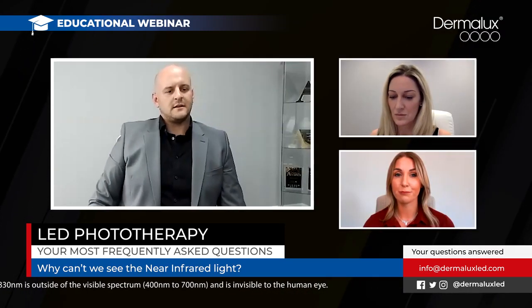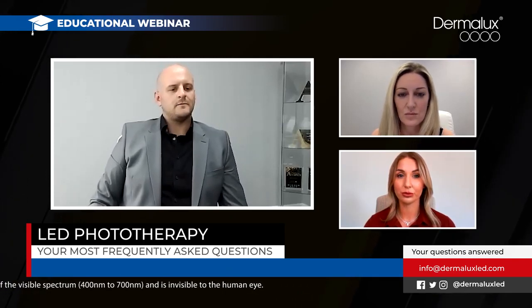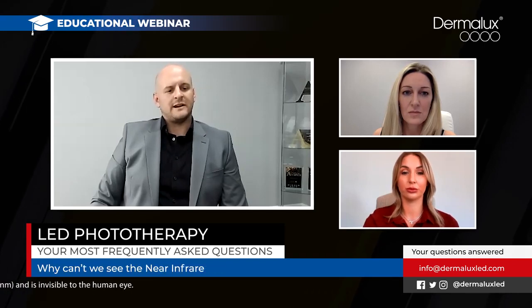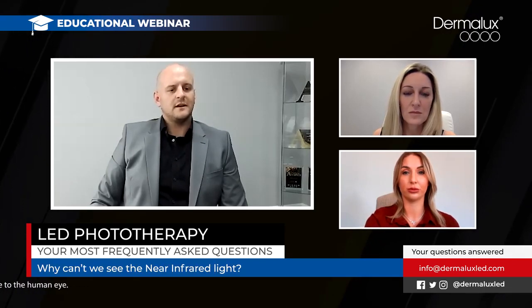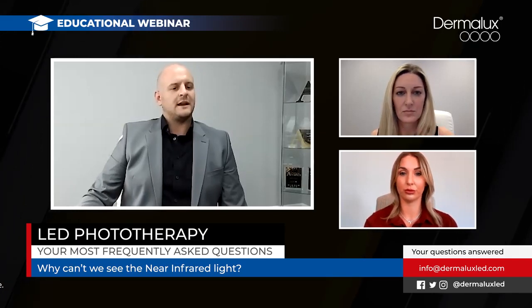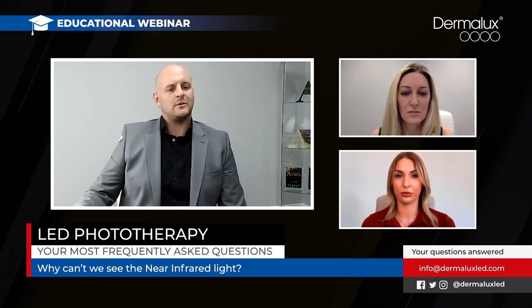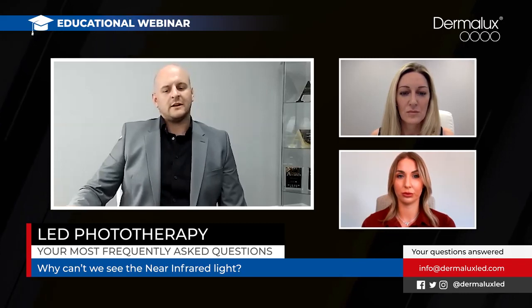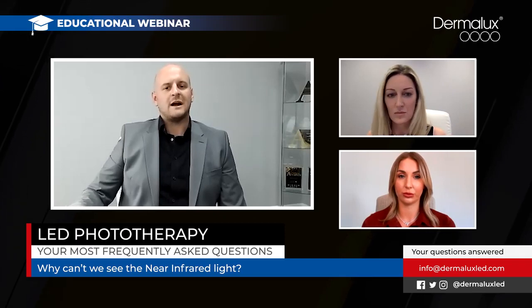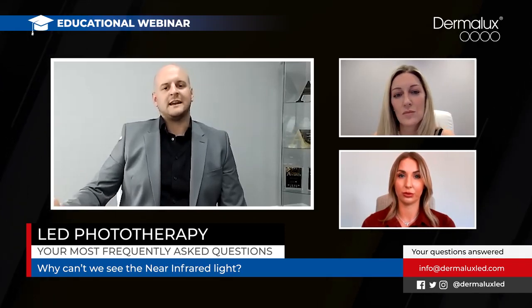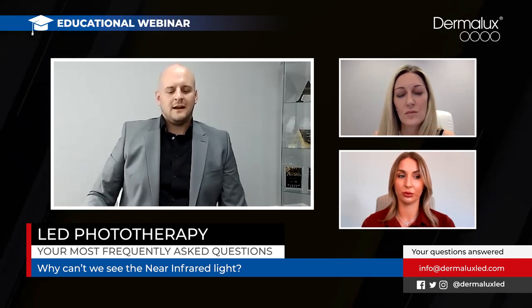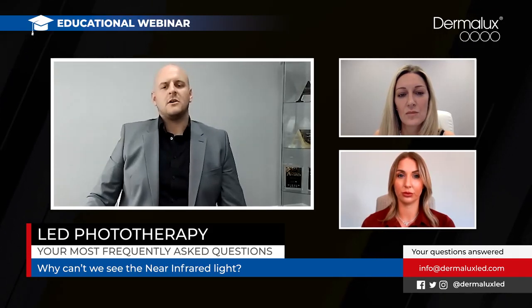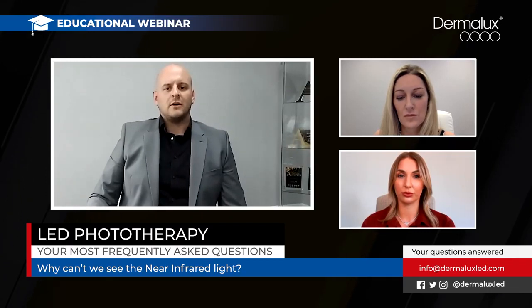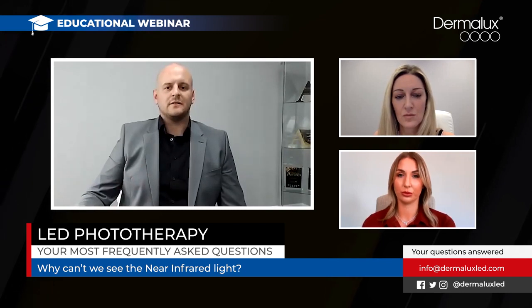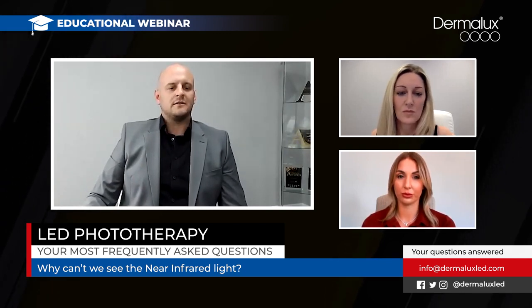So just to add to that, Leigh touched on something about the infrared light being very powerful. Because of new standards surrounding medical devices that come into market, there is actually an applicable standard for manufacturers to state the optical radiation that's being emitted from the device. You'll notice across our devices that we have a yellow warning label on there, which shows a risk group classification and the overall amount of power that's being delivered over the length of the treatment. If you take a look at any LED device in the market, this labeling should be clearly marked around the aperture of where the LED light is being emitted, and that acts as an indication of the overall power that's being emitted from the device. It's easy to get lost with the numbers when looking at marketing literature, but we've now got good rules in place, good governance around the actual device and how a manufacturer is to state its figures. And I would recommend that when buying an LED device, definitely take a look at that.